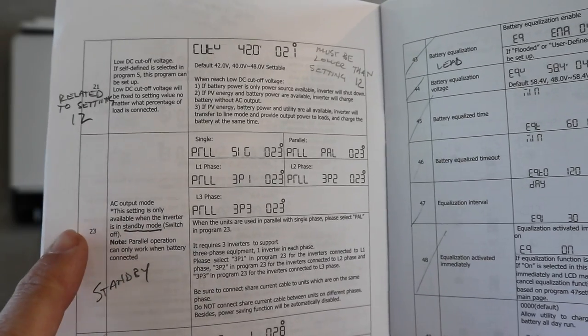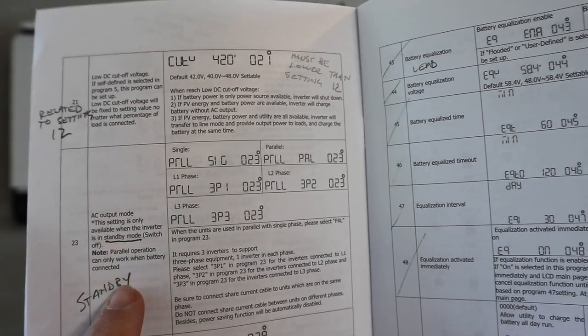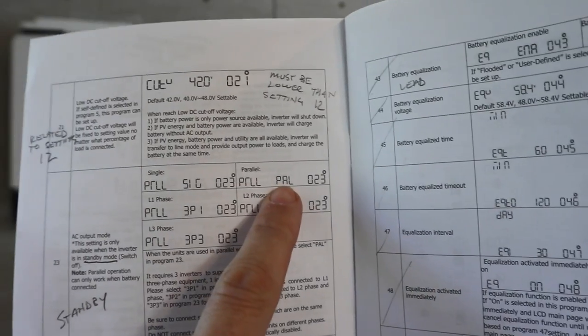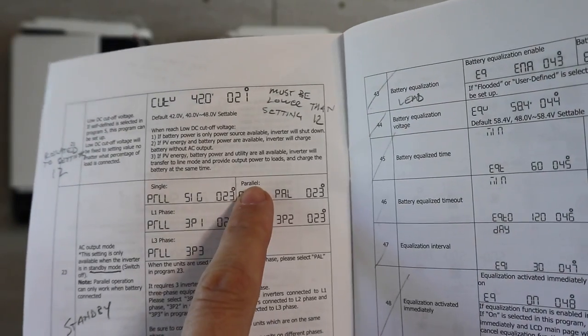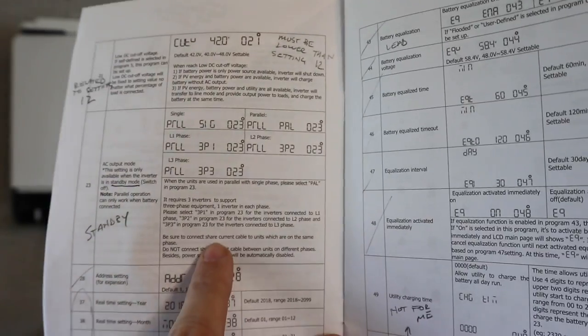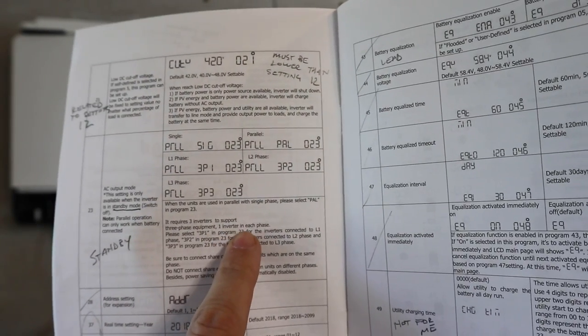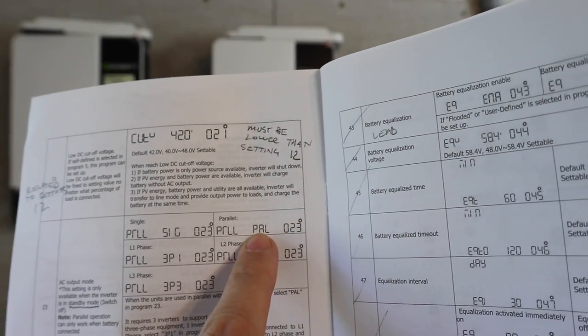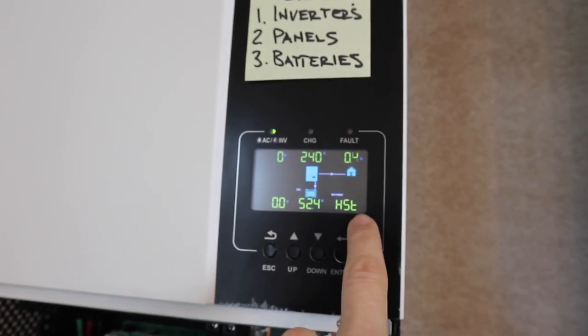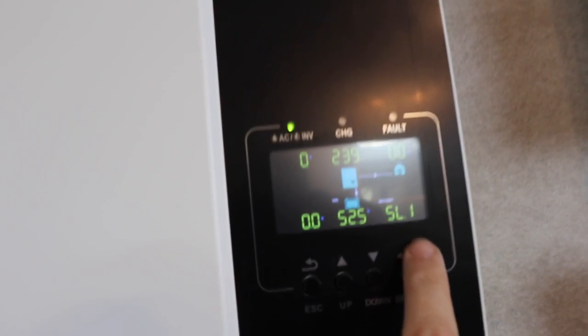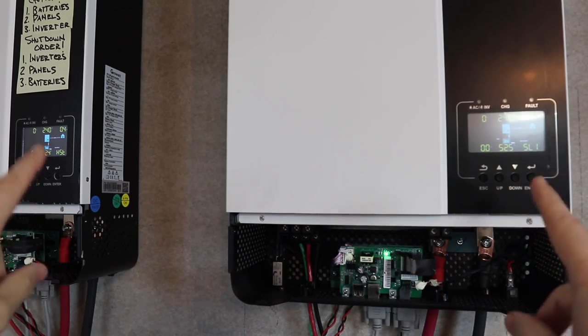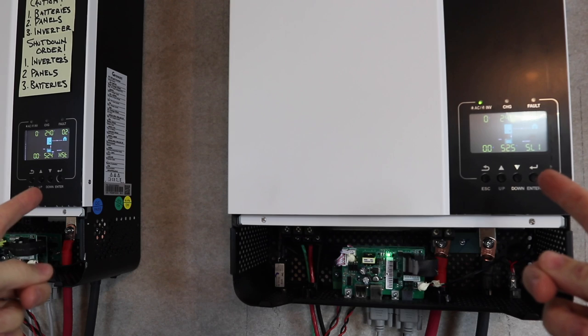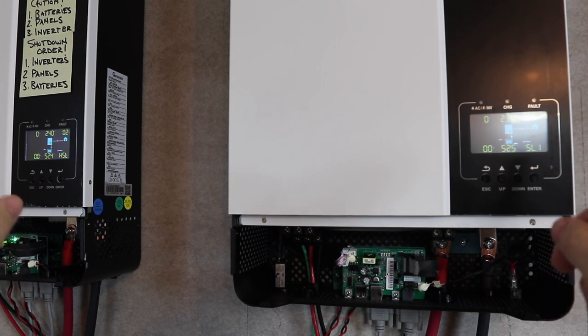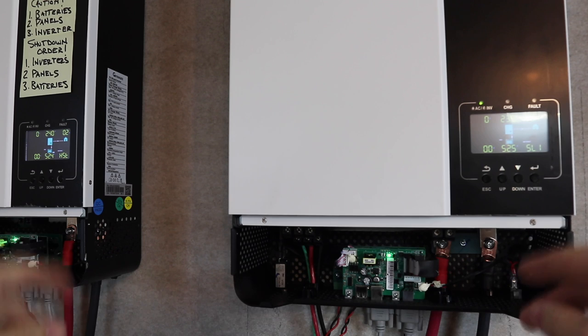So we're gonna work on function 23, and that needs to be in standby. And what we're gonna do is set them for PAL, which is paralleling, and that's for two inverters. Three phase with three inverters requires a different setting, but we've got two, so we're gonna do this one right here. So this first inverter over here is the one I want set at master. So that's set at the master. And then this one over here is slave number 1. Now we're going to flip both of these off and they'll stay in standby mode for that period of time I told you. And we're going to go to function 23 and set it to PAL.